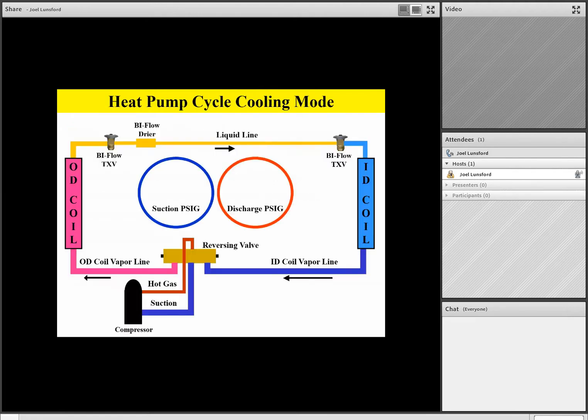So at this time, let's go ahead and review the heat pump cycle for the cooling mode of operation. You'll notice right in the middle of the screen, you'll have a suction gauge and a discharge gauge, and those will both be displayed as pounds per square inch gauge. On the left side, the suction gauge has a blue outer ring indicating it's low pressure, and on the right-hand side, the gauge has a red ring indicating it's high pressure discharge.